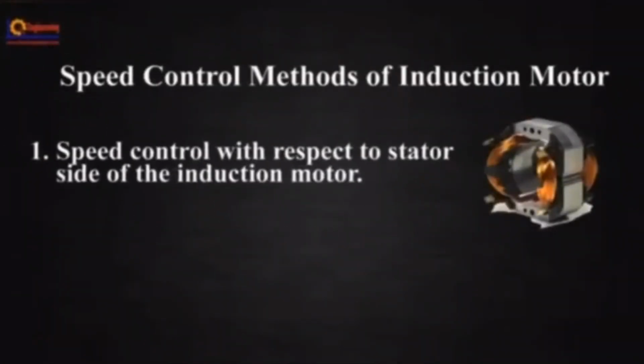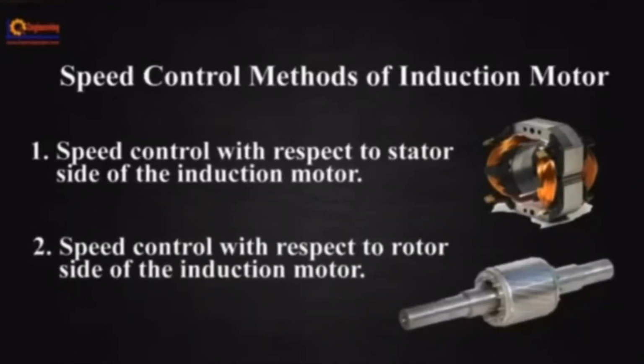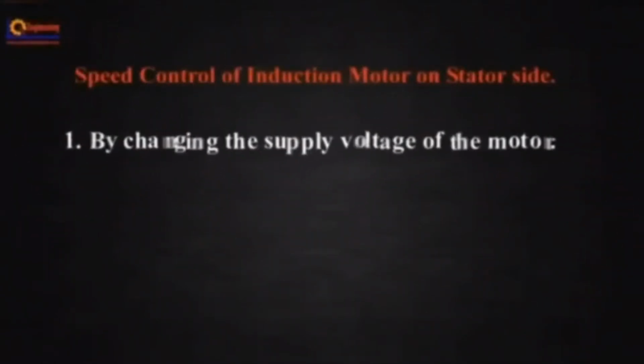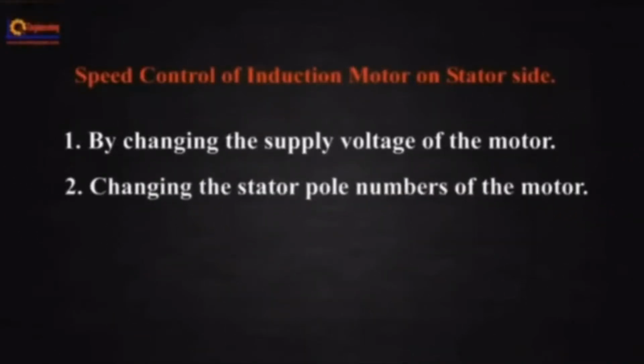Speed control with respect to the stator side of the induction motor. Speed control with respect to the rotor side of the induction motor. The speed control of an induction motor by controlling the stator side can be subdivided into several speed controlling methods, such as changing the supply voltage of the motor, changing the stator pole numbers of the motor, and changing the frequency of the supply side of the motor.